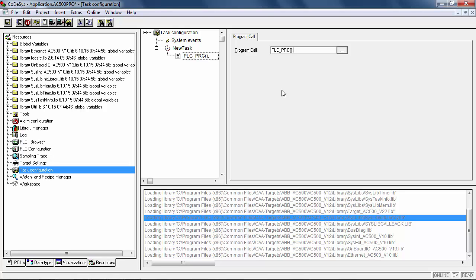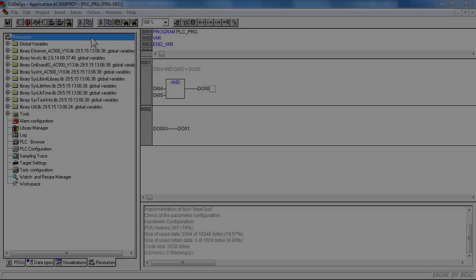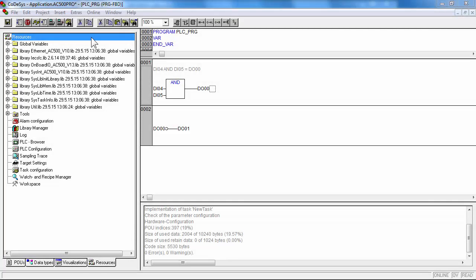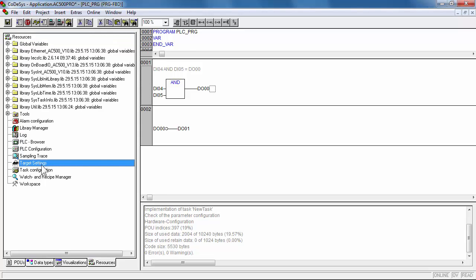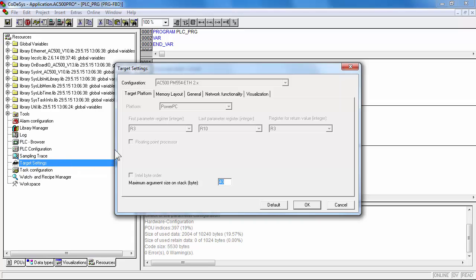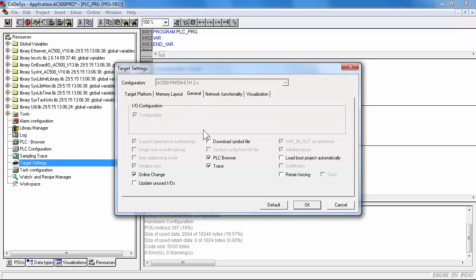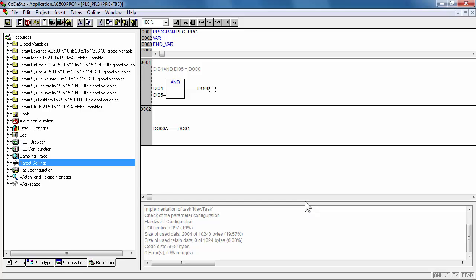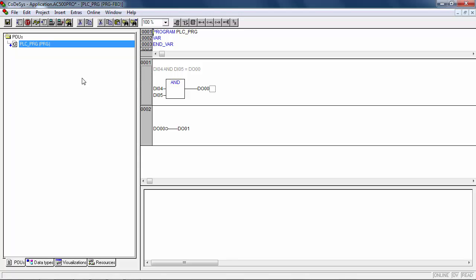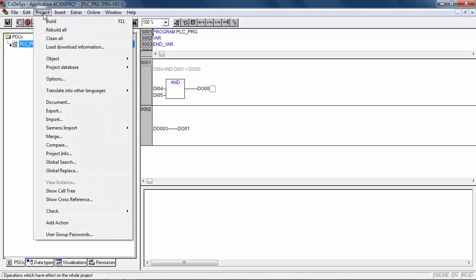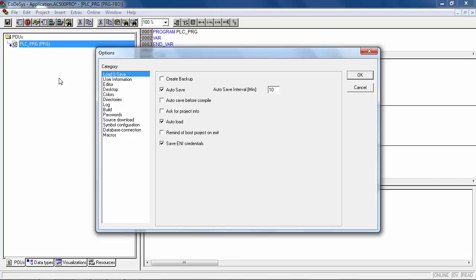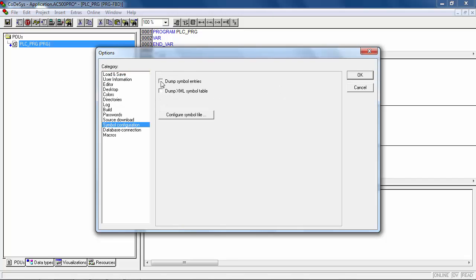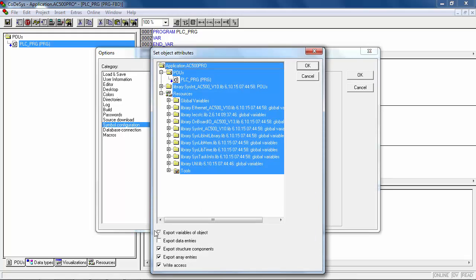The communication using ABB code sys protocol is possible only if a symbol file is present in CPU. This file includes all the variables which will be exchanged. At first, we need to select the download symbol file option in target settings tab of the project in order to download this file with program files into the memory of the CPU. The next step is to create and define this symbol file. Let us look at the procedure to realize it in project tab menu and then options select symbol configuration in navigation and follow up the next steps of the configuration for adding the wished variables of the project.